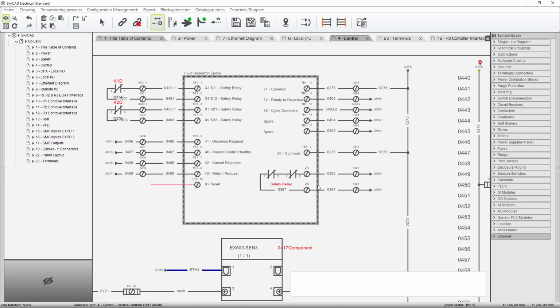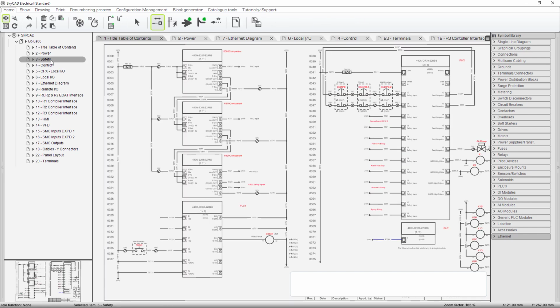Now, this isn't totally built into this epoxy dispense system. So when I commission this, I'm going to have to go in and actually do a little hand work with wiring to make these 2 terminals suffice as a signal from this e-stop safety going back to the main panel. So this is channel 1 and channel 2 from the main safety relay in the epoxy dispense system. I'm using those 2 channels in series to send a signal back to my safety circuit, which we'll get to eventually, and this is in the safety sheet. And see, here's the epoxy e-stop right here.